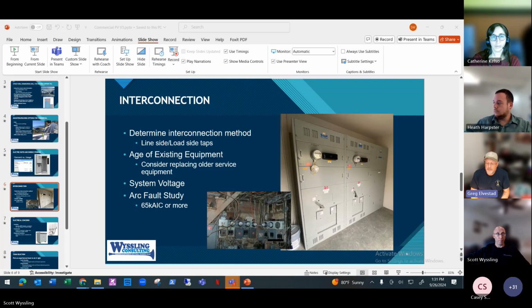It's a very real thing. Why do I care? The condition being a knife switch. Your basic unfused knife switch is only listed at 10,000 amps interrupting capability. And while that may seem like a lot, and it is, when you have a 65,000 amp fault energy capability being delivered to the building, even 100 feet away from the panel, there is the possibility, if there was a fault on the circuit that switch is intended to interrupt, of that fault current being in excess of 10,000 amps. And the last thing you want is for that thing to fail in your hands as you're opening that switch. There's a lot of variables and statistical things that have to fall in place for that to occur. But the bottom line is we don't engineer to what's the probability. We engineer to what can happen. And at the end of the day, that's the only safe way to engineer things, and that's the only way we're going to recommend stuff.